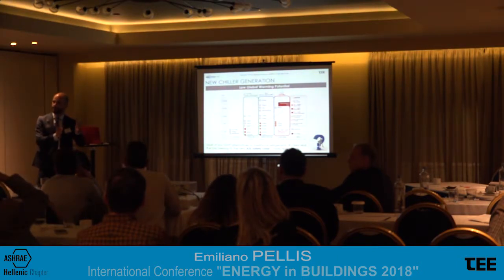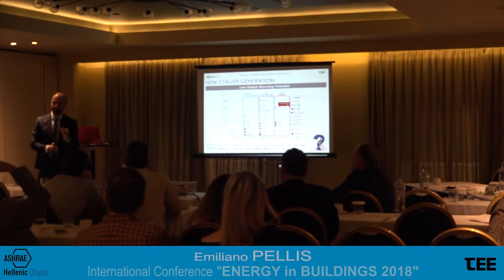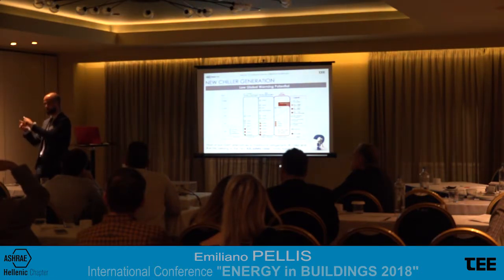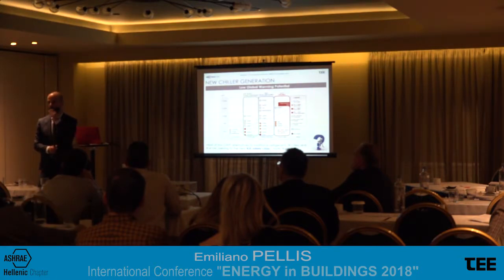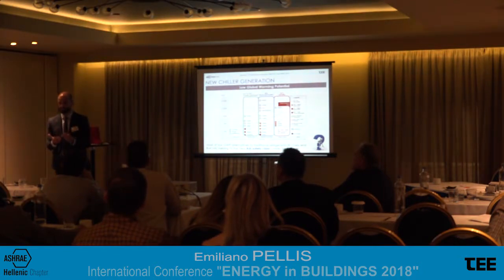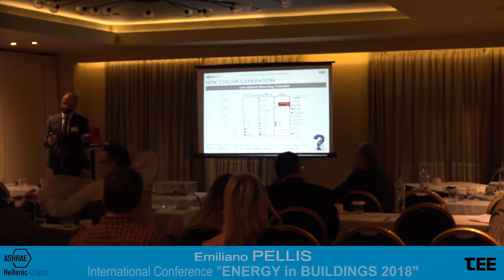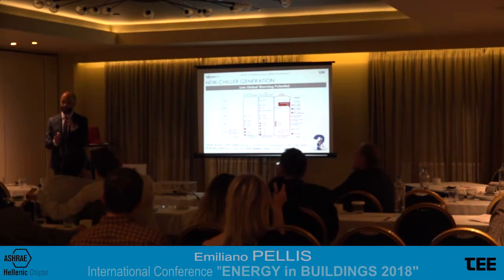Okay, this is on one side. In any case, in the standard EN378, you will find some dedicated prescriptions. For example, if you have water-cooled chillers, intended to be in a technical room, you will have to install additional ventilation in the electrical panel of the unit, and you will have to install, for example, leak detectors. So the refrigerant in the end is flammable, but mildly flammable, and the risk level is low, but in any case the norm will tell you some additional cares that must be implemented in the room.